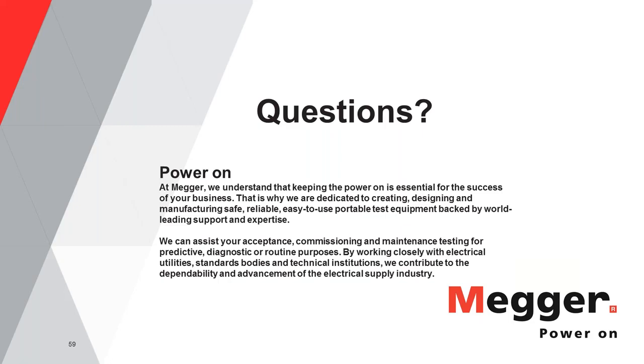All right, the next question is, I had a plant engineer complain that primary injection of his molded case circuit breakers, he claimed, was followed by a high failure rate, so he didn't want to test them anymore. Any thoughts on that? That's a very interesting question, because to answer it with reasonable justification, we need to understand what kind of failures we are talking about. Remember, when we talk about circuit breakers, you could have different types of failures. There could be a problem because of heating that could lead to problems with the contacts. There could be insulation failure, or the breaker couldn't handle the amount of current that it is supposed to handle.